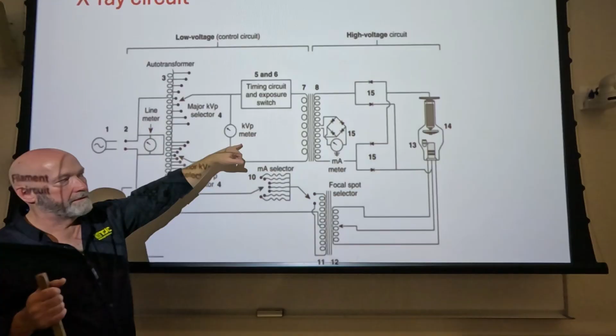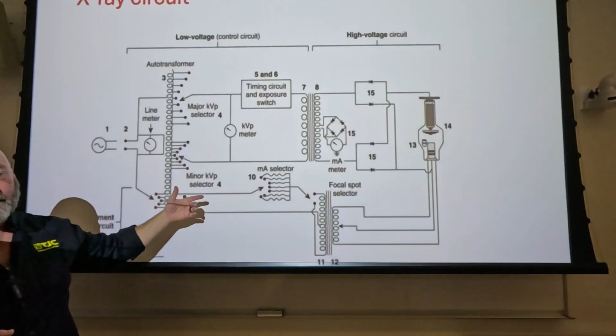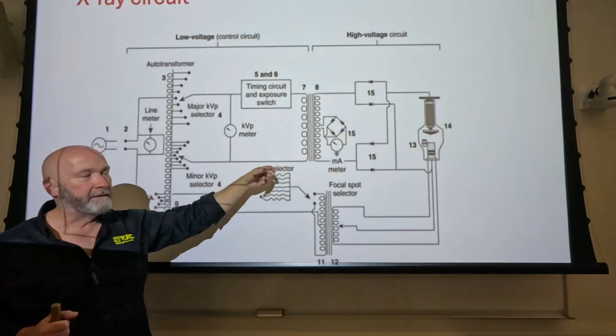So it comes out of there. We've got a kVp meter here, but where is our kVp made? The secondary side, right? So we don't have kVp yet. Why do we call it a kVp meter? More specifically, we call it a pre-reading kVp meter because it's not reading kVp, it's reading voltage in anticipation of it becoming kVp. So if our voltage is correct here, then we know what it's going to be over here, because this is a variable turns ratio and that's a set turns ratio transformer. So we know exactly how much of a boost we're going to have here. If we have the right voltage here, we can automatically assume it's going to be the right kilovoltage over there. It's a pre-reading kVp meter. It doesn't matter that it's reading voltage. We know how much of a boost it's going to have once we send it through the high voltage transformer.